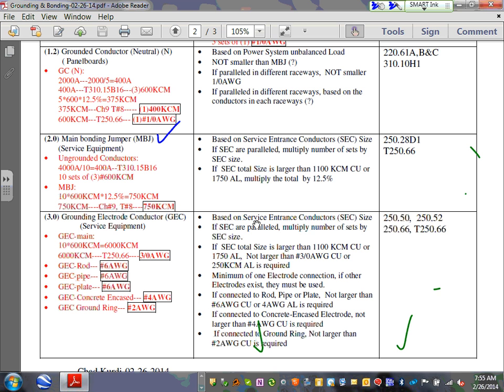How do we size it? We size it based on the service entrance conductor. And if the service entrance conductors are parallel, multiply the number of sets by the service entrance conductor size. And if you're larger than 1100 kcmil copper or 1750 aluminum, you have to start using the 12.5%. You guys remember using this? We had an example where we used the 12.5%. And where does this information come from, Karen? It comes from 250.28(D)(1) and Table 250.66. Any comments, guys? Any questions about 2.0?